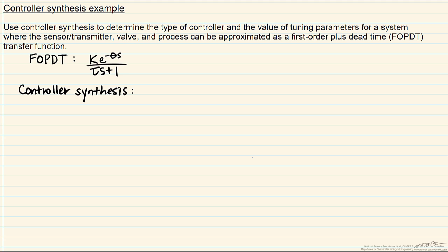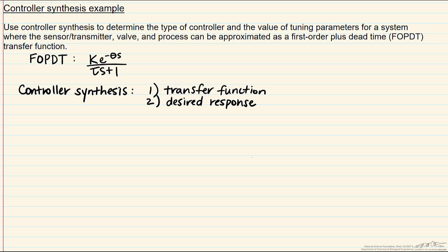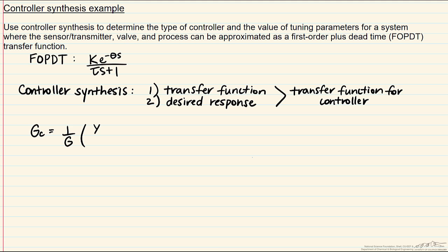The methodology of controller synthesis is that we pick two things. We pick a process transfer function — which also includes the valve and the sensor transmitter — and we pick a desired response. Generally our default desired response is 1/(τc·s+1). From those two values we can get the transfer function for a controller in the PID family, including the tuning parameters. The formula is: one over G, multiplied by (y/x) divided by (1 - y/x), where y/x is 1/(τc·s+1).